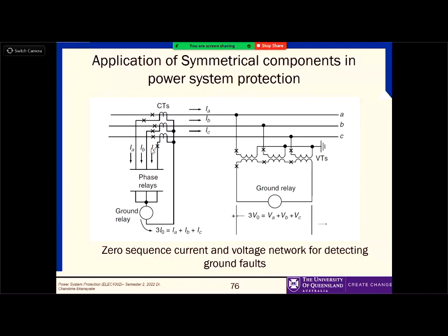Here, you don't know where the neutral point of this whole system is, because you are somewhere midway where you can see the three transmission lines, that's all. You don't know whether it is delta connected or Y connected. So we connect three CTs here, and the CTs are Y connected, which we can do because the CTs are with us now. The secondary terminals of the CTs are now Y connected, and all four wires feed a measuring system. Inside that measuring system, the neutral point goes through a relay called a ground relay.